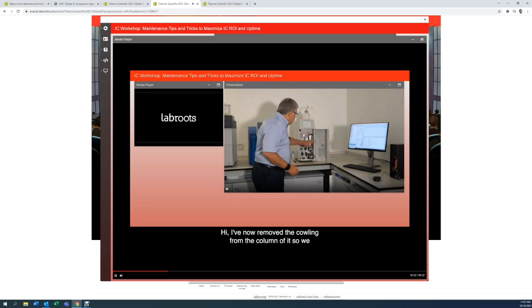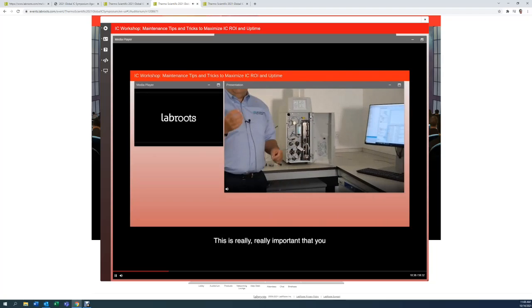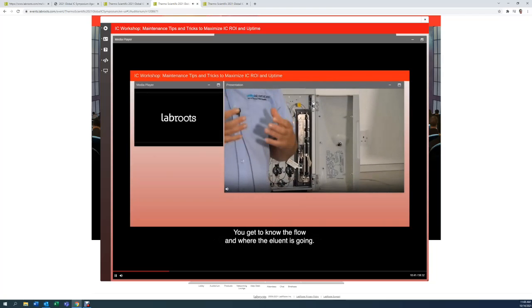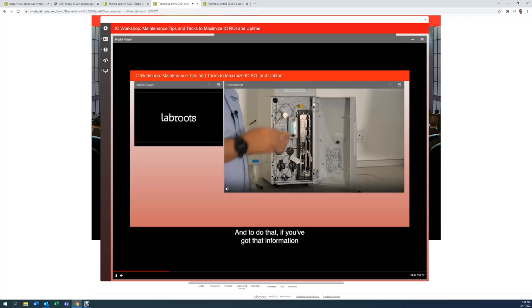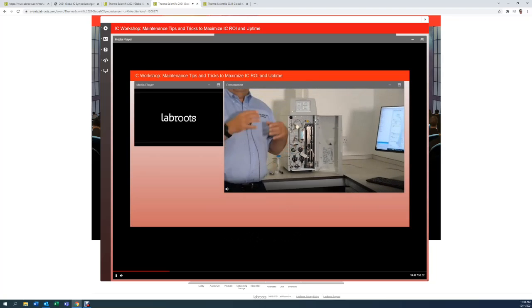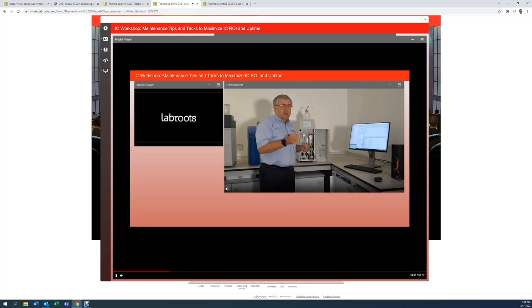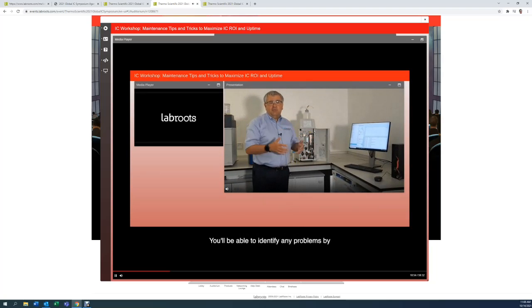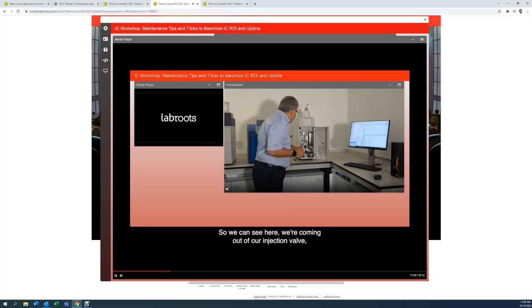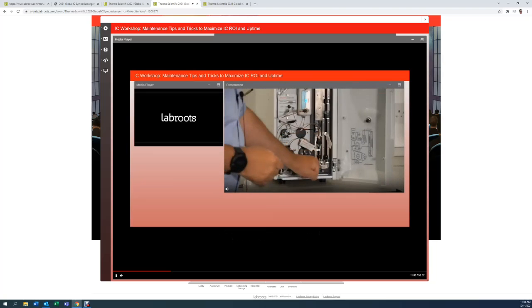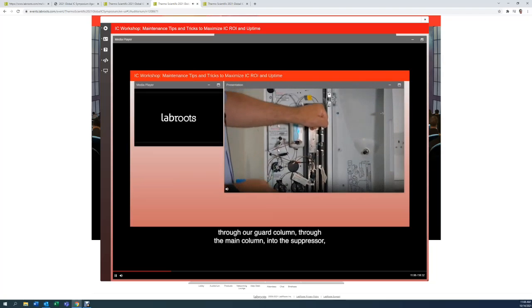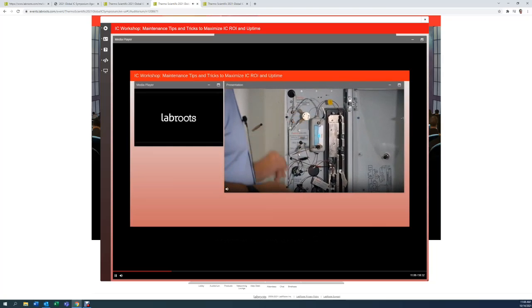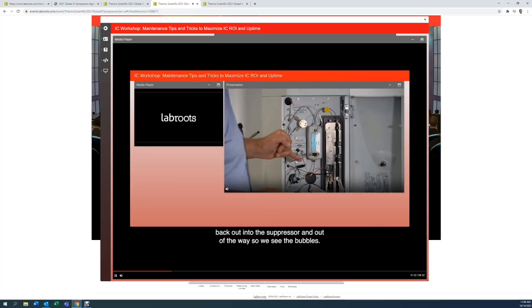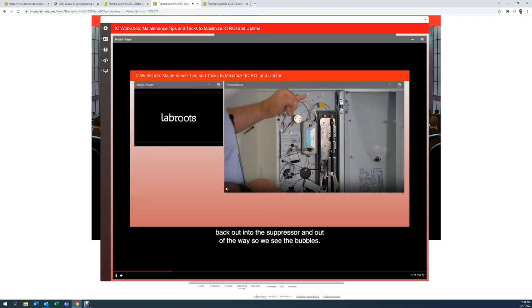Hi, I've now removed the cowling from the column so we can see the columns very clearly here. This is really important: you need to get to know your ion chromatograph, know the flow and where the eluent is going. If you've got that information, troubleshooting the system becomes that much easier. By knowing where the eluent should be going, you'll be able to identify any problems by seeing where it's not going. So we can see here we're coming out of our injection valve, through our guard column, through the main column, into the suppressor, out of the suppressor into our cell, back out into the suppressor, and out of the way so we see the bubbles.